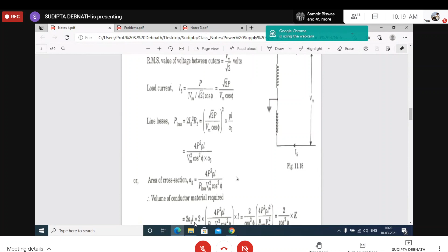Okay, AC single phase without midpoint earth. Okay, so the conductor material required for AC systems: there are 2 types of AC 2-wire systems. For both the systems, the amount of conductor material is the same. Okay, but this was not the case for the overhead transmission line. Why? In the overhead transmission line there was a difference because the voltage was to be kept constant between one conductor and earth, but here, due to the earth point, the voltage is changing.